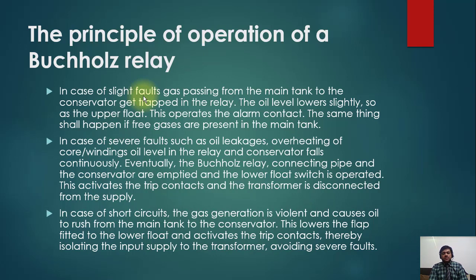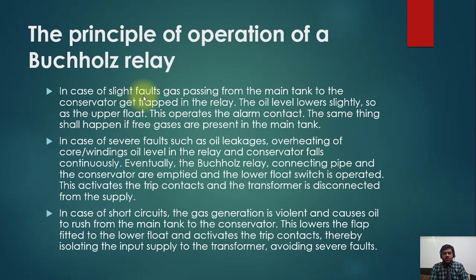There are two contacts in the Buchholz relay. For a light fault, one contact operates and initiates an alarm. For a heavy fault, the second contact operates — heavy oil flows with pressure, and the transformer trip is activated immediately. In the case of a short circuit, gas generation is violent and causes an oil rush from the main tank to the conservator tank. This lowers the flap fitted to the lower float and activates the trip contacts, thereby isolating the input supply to the transformer and avoiding severe damage.